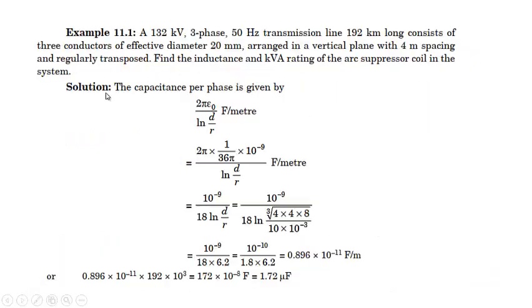Let us try to do a numerical on the same, that's the Peterson coil. We have a 132 kV 3-phase 50 Hz transmission line, 192 km long. It consists of conductors whose effective diameter is 20 mm, arranged in a vertical plane with 4 meter spacing and regularly transposed. So find the inductance and kVA rating of the arc suppression coil in the system.